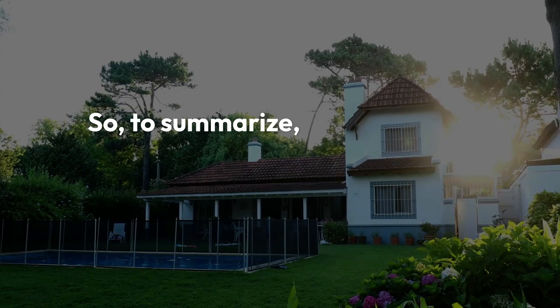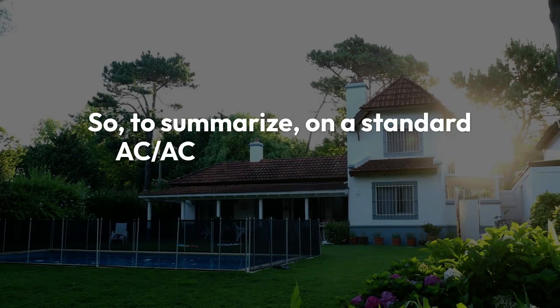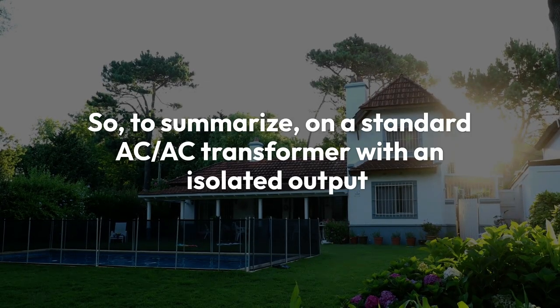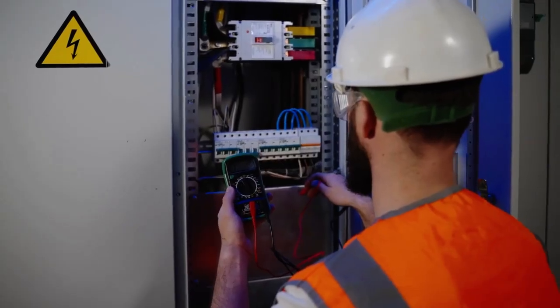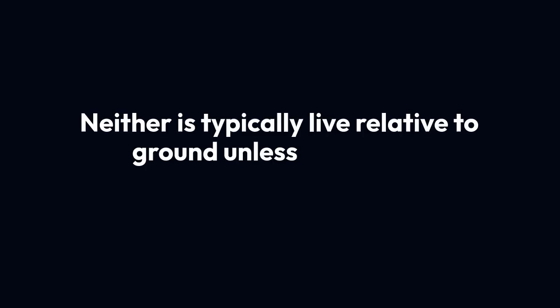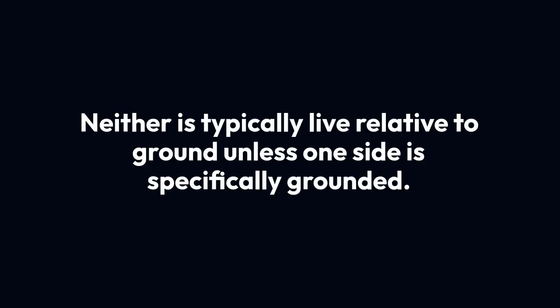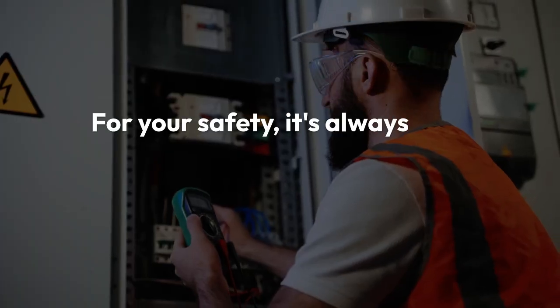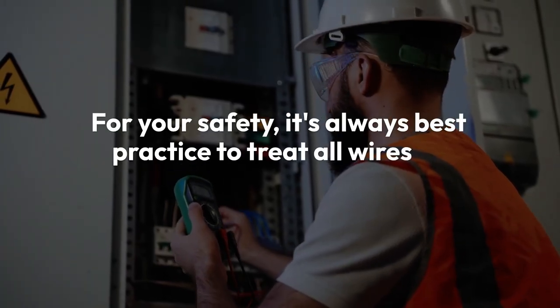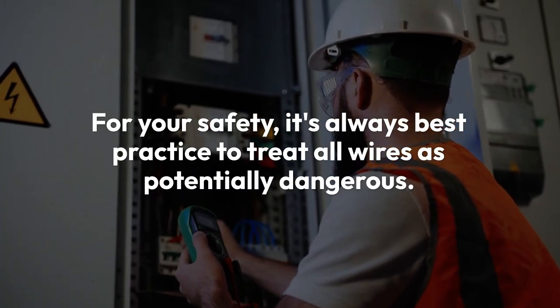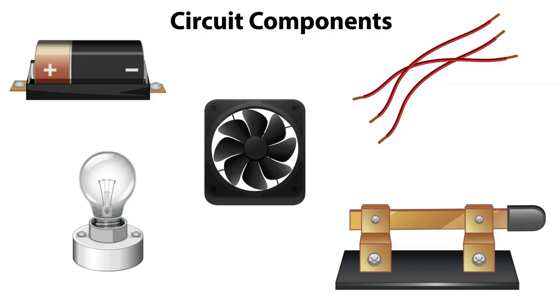So, to summarize, on a standard AC/AC transformer with an isolated output, both wires carry voltage, but only relative to each other. Neither is typically live relative to ground unless one side is specifically grounded. For your safety, it's always best practice to treat all wires as potentially dangerous. Always use a multimeter to test for voltage before touching any wires. Always unplug or disconnect power before working on any electrical circuit.